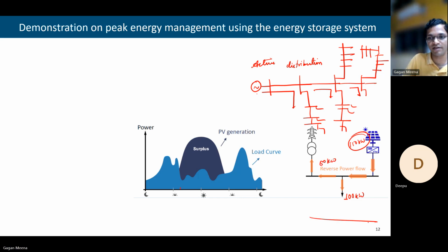Earlier, however, if the load is 100 kilowatt and due to cloud cover the generation is only 80 kilowatt, then the remaining 20 kilowatt will come from the grid, from the substation. So this is manageable. This is as per what we have been working with till now, the unidirectional power flow, the passive distribution system. But now, because of excess PV generation, which is more than the load requirement, power is flowing back to the substation. This is reverse power flow.